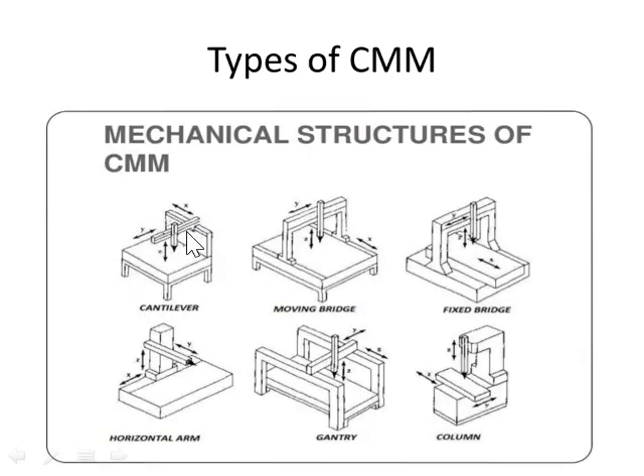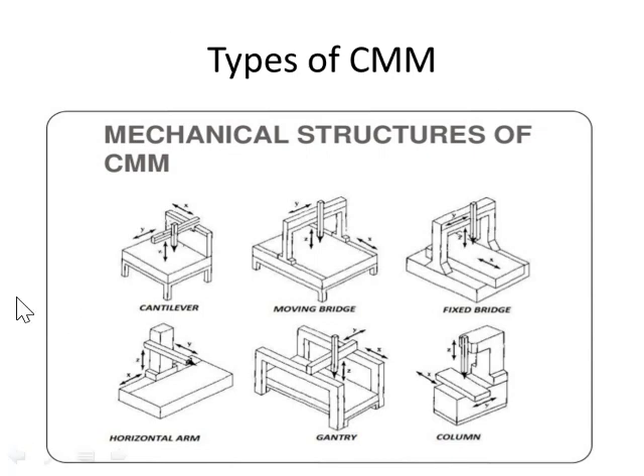This is the CMM machine in the cantilever type. Cantilever means one end is fixed and the other end is free. This column can move in all directions — X, Y, and Z — all three directions. That's why we call this the cantilever type. I am placing a work object here, and I need to measure the profile, like complicated shapes.